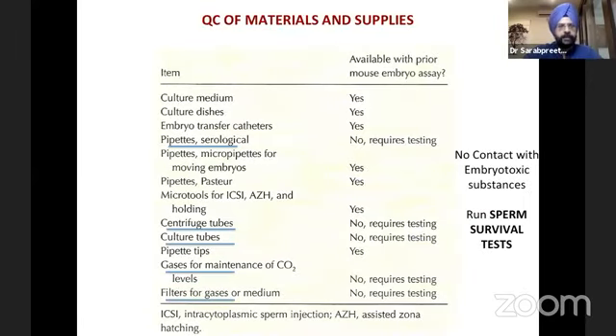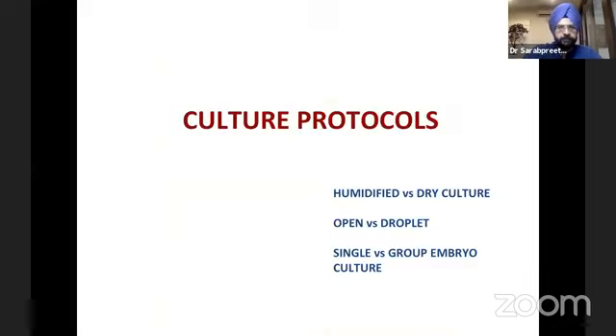QC of materials and supplies. There are some materials in the lab which are not embryo tested, such as serological pipettes, centrifuge tubes, culture tubes, gases for the maintenance of CO2 levels, and filters for gases. The embryo should never come in contact with any embryotoxic substances, so for the things I mentioned, you should always run a sperm survival test because they are not embryo tested. So run a sperm survival test on a new batch and then start using it.